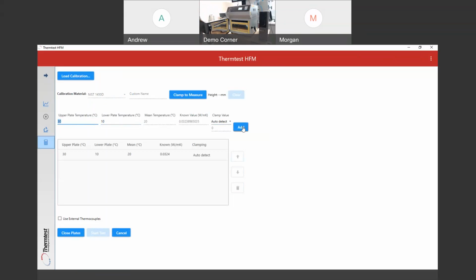All right. Here you can set a specific thickness, but you wouldn't do that with your calibration anyway. Well, I say that, but somebody might do a specific thickness on calibrate. It just depends on what you're doing. But typically on the calibration, you let it do its automatic clamping, so we'll leave that on auto detect. And if I was going to do more temperatures, I could increase this by 10 degrees, and you can see it automatically adjusts the following ones like that. Then it would automatically go through and do each one. Okay, so I'll cancel these because we don't need them right now. But now I would close plates, and you'll see it close plates.